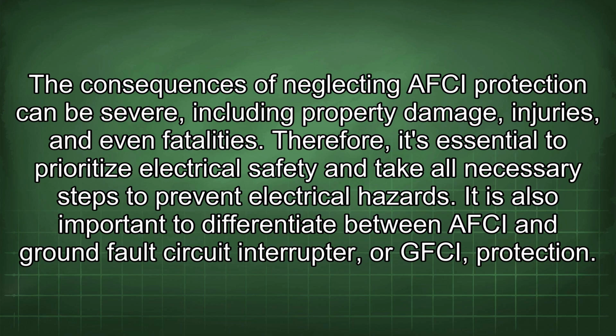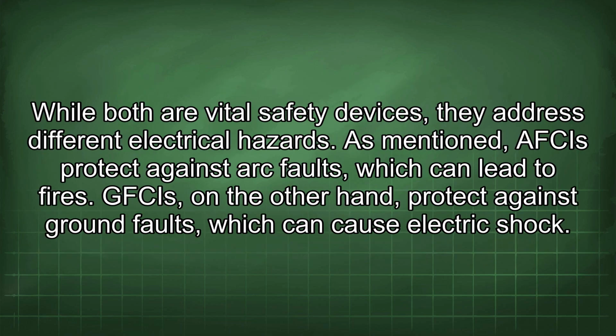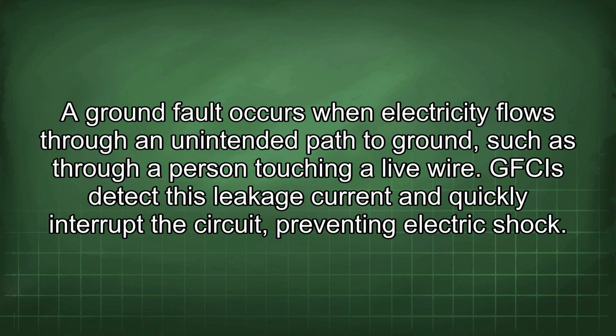It is also important to differentiate between AFCI and ground fault circuit interrupter, or GFCI, protection. While both are vital safety devices, they address different electrical hazards. As mentioned, AFCIs protect against arc faults, which can lead to fires. GFCIs, on the other hand, protect against ground faults, which can cause electric shock. A ground fault occurs when electricity flows through an unintended path to ground, such as through a person touching a live wire. GFCIs detect this leakage current and quickly interrupt the circuit, preventing electric shock.